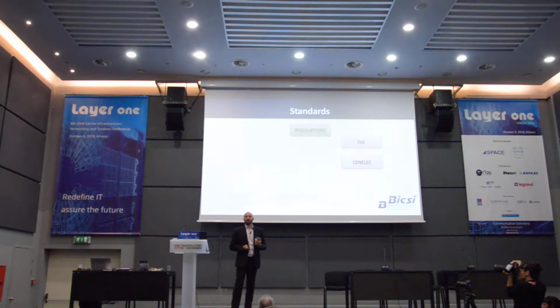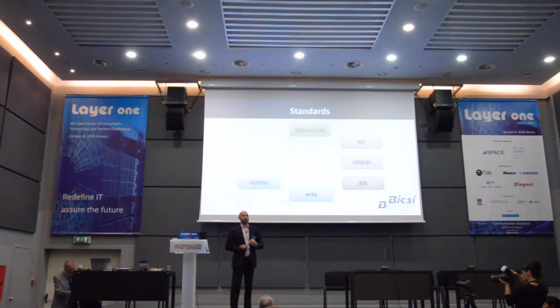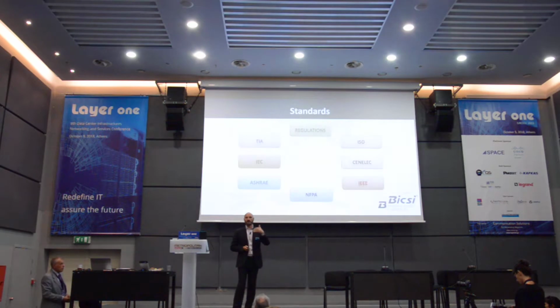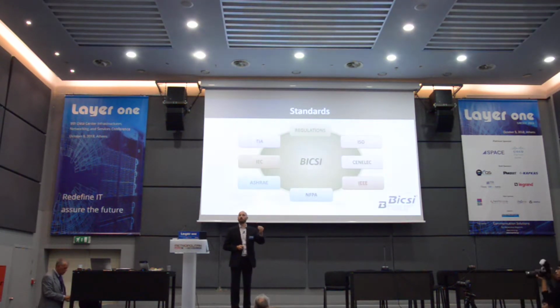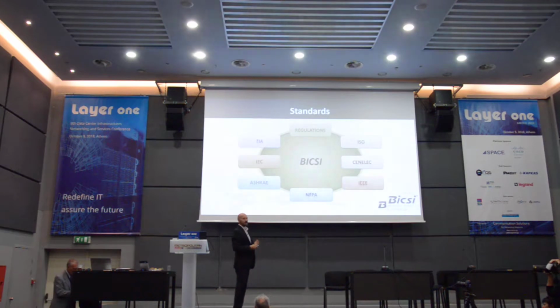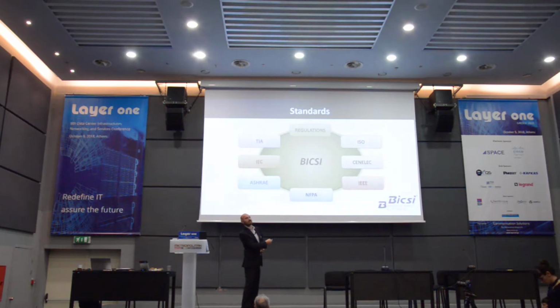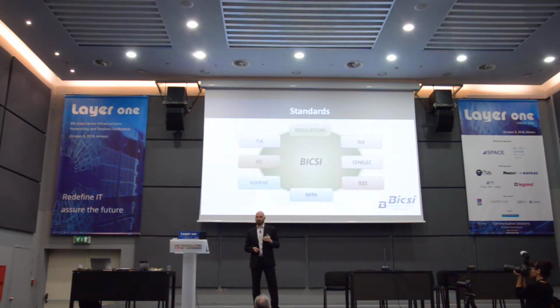And what it's about is best practice. So when you start a project, you first have the regulations, that's the mandatory part. Then you start to look into other standards, and you might follow some ASHRAE recommendations for temperature and humidity, NFPA in the US for fire rating, different ones in Europe. And then you'll choose to follow either ISO, CENELEC, or TIA for the cabling. All of those are minimum requirements. They tell you if you don't do it this way, you're not guaranteed it will work.